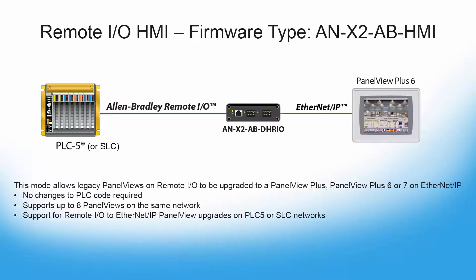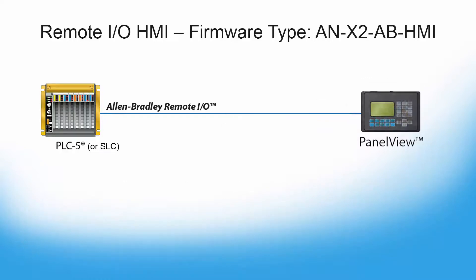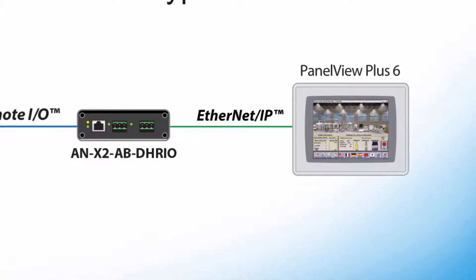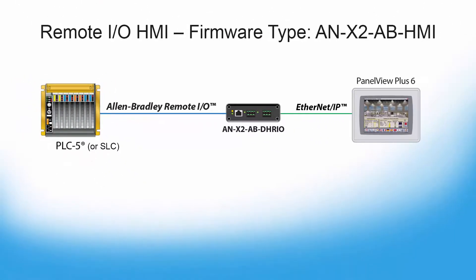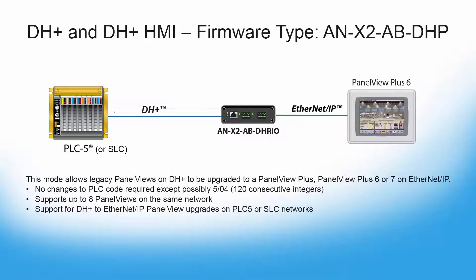Next we have the ANX2AB HMI. This is another mode intended for just one thing: upgrading RIO panel views to Panel View Plus 6 or 7 on Ethernet IP, allowing you to add the latest panel view HMIs to your RIO network. This should only be used for situations where you're integrating HMIs over Ethernet IP to a RIO network. If you want to add HMIs to a Data Highway Plus network, you would need to use the next firmware on our list.